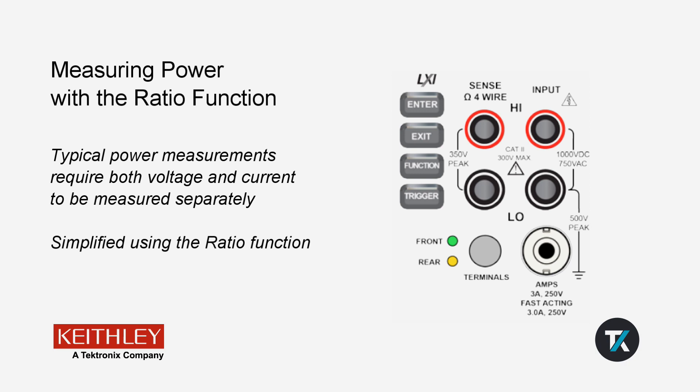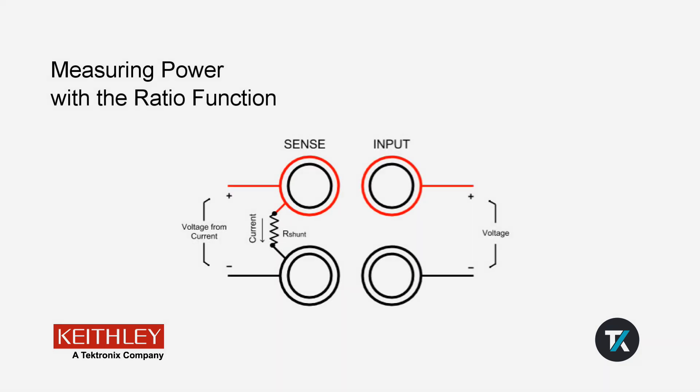This is possible because the ratio function measures the voltage across the sense terminals and the voltage across the input terminals at the same time. We will use a shunt resistor on the sense terminals to measure current, and we'll measure voltage on the input terminals.